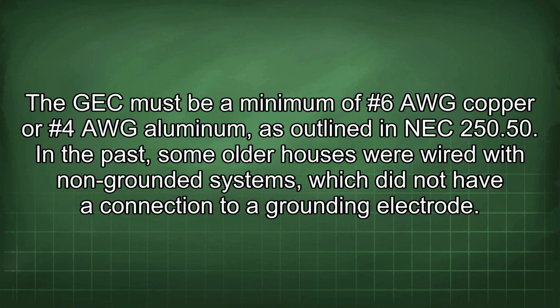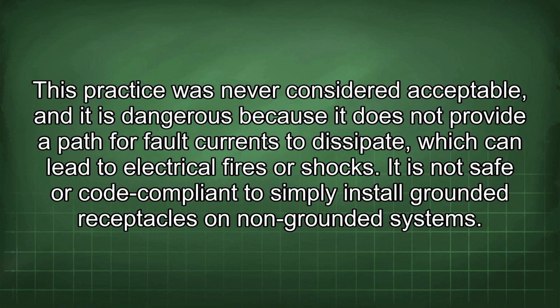In the past, some older houses were wired with ungrounded systems which did not have a connection to a grounding electrode. This practice was never considered acceptable, and it is dangerous because it does not provide a path for fault currents to dissipate, which can lead to electrical fires or shocks. It is not safe or code compliant to simply install grounded receptacles on non-grounded systems.